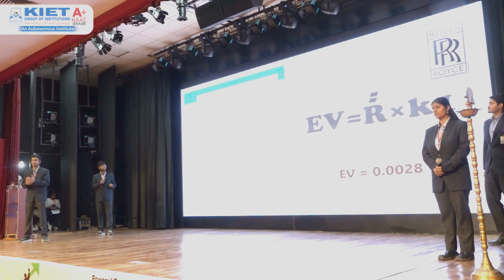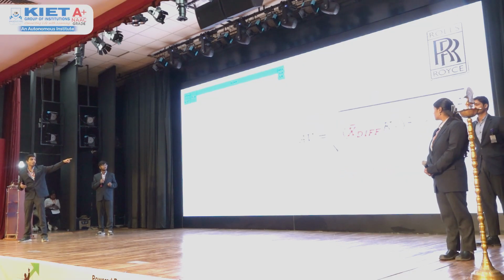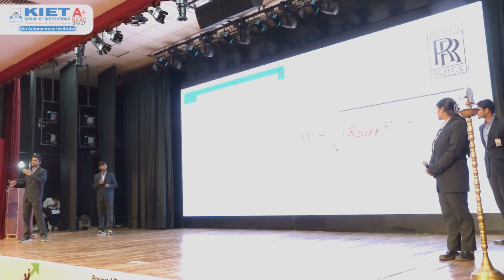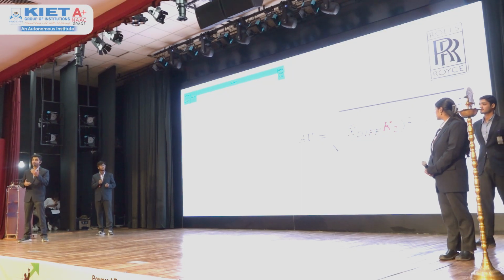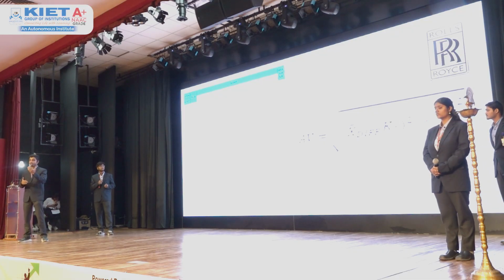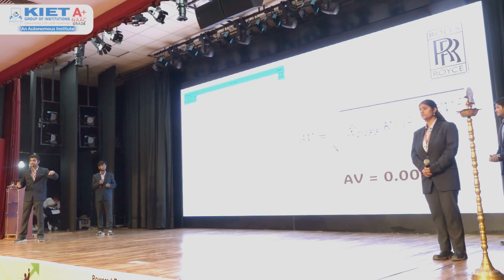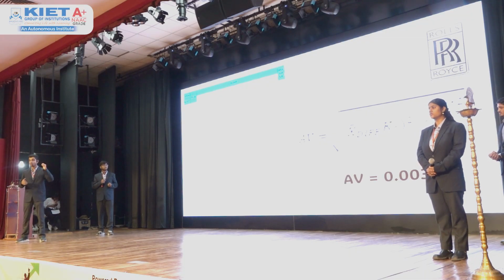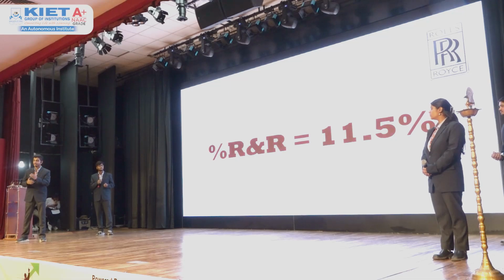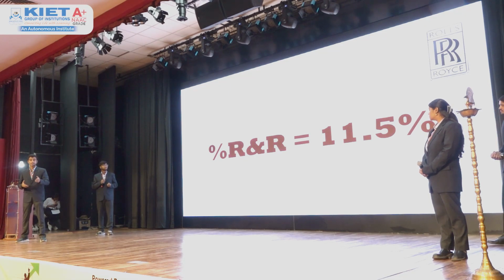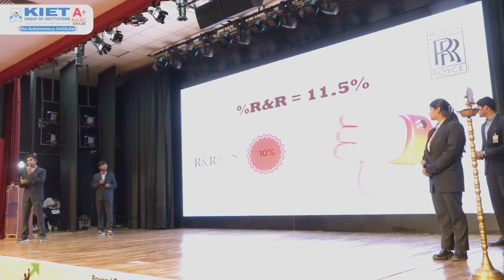And for the appraiser variation, there is a formula where X bar diff stands for the difference between the maximum part average and the minimum part average, K2 stands for a constant depending upon the number of appraisers we are taking, and nr is the product of the number of trials and the number of parts, whose value comes out to be 0.003. By putting these values in the formula of gauge R&R, the percentage variation of gauge R&R comes out to 11.5%, where 8% of the variation was by the appraiser.